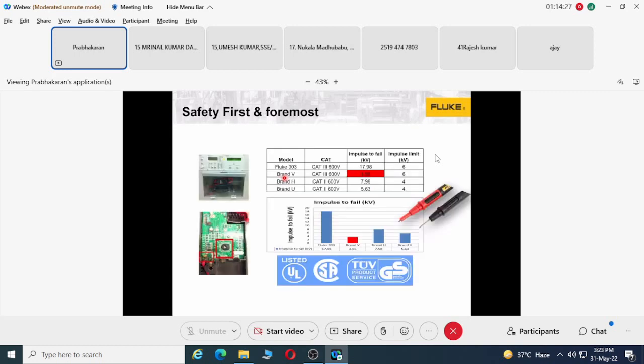When I say safety standards, you can see the cheapest clamp meter of ours we have tested. This one is actually designed for category 3 and 600 volts. We could test it up to 17 or 18 kV, and it's supposed to withstand only 6 kV, and we did that test, and then we realized that we could go up to that level. But we have also conducted a similar study for our own understanding, and we realized that there are brands which actually fail much before the designed levels.